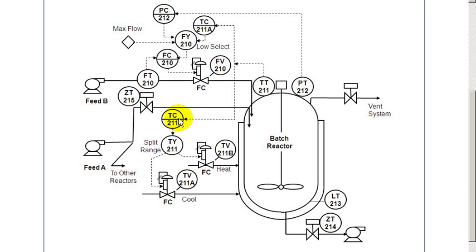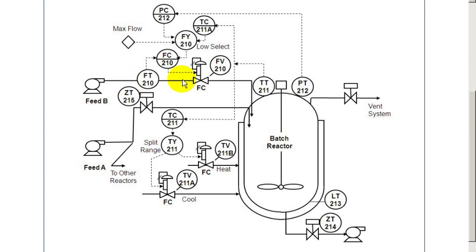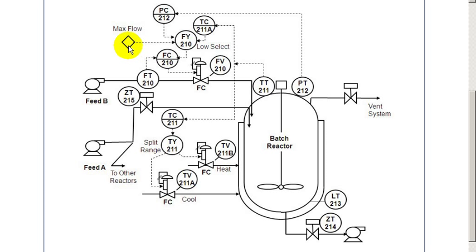And at that point, the feed is cut off and the temperature controller is released to drive the temperature of the batch up to a reaction temperature. At some temperature, once it's reached, then a second material is added, a catalyst to the reactor. The flow rate is determined by the operator's set maximum flow.